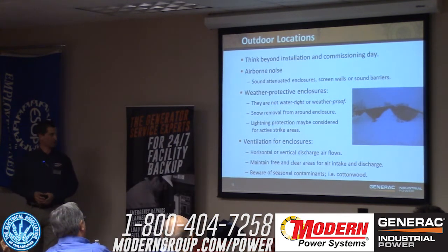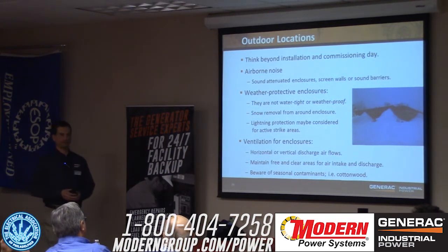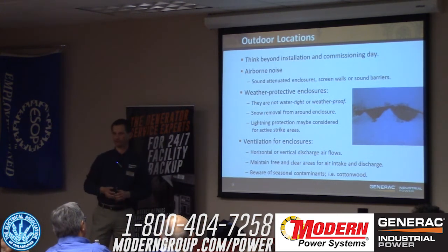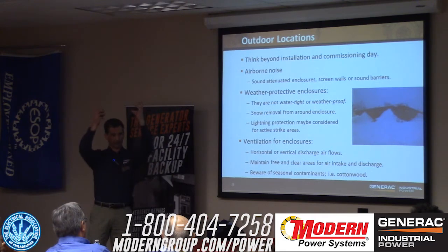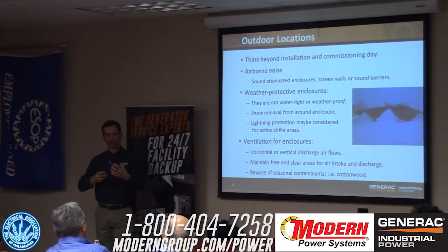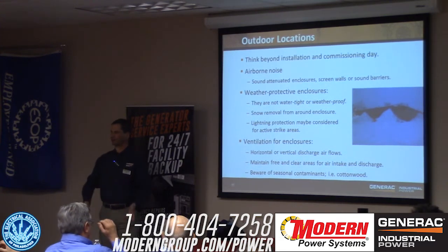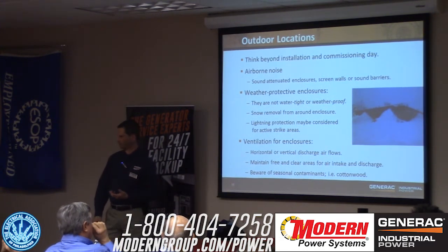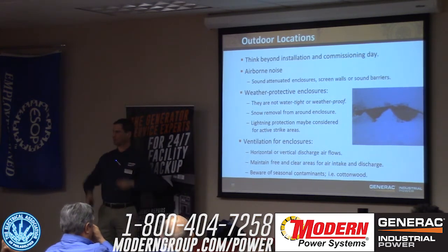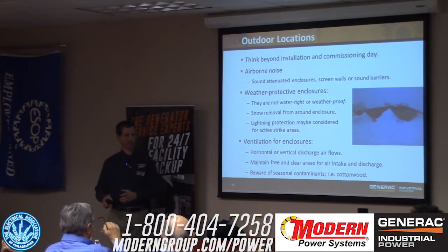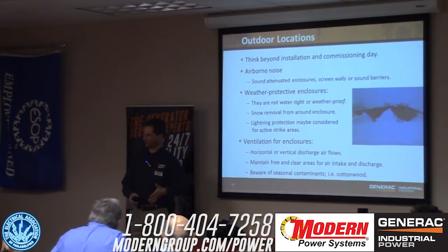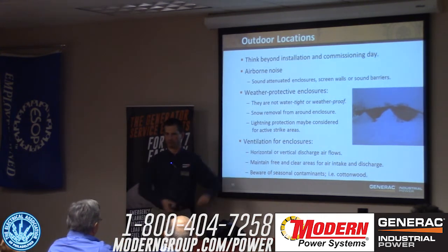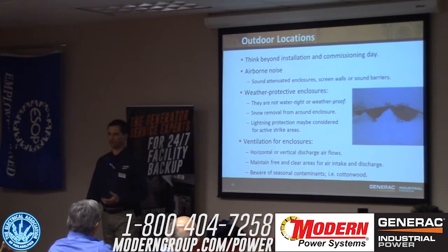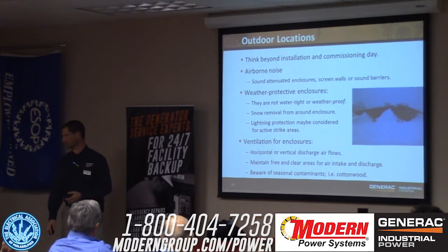In terms of ventilation, think about the enclosure. Most of them now will vent vertically upwards, so you're taking your radiator exhaust and your exhaust gas and pushing it straight up. So you're really starting to disperse and diffuse that exhaust gas, getting it away from the ground, which helps with any kind of objectionable odors and whatnot. But you've got to have clear space above you if that's the style of enclosure that you use. There are still some manufacturers out there where you'll just have a radiator, maybe some louvers, and it's all going to blow horizontally. But that's becoming less and less common because they're just so loud, and everybody wants their gen set to be quiet, at least in some respect.